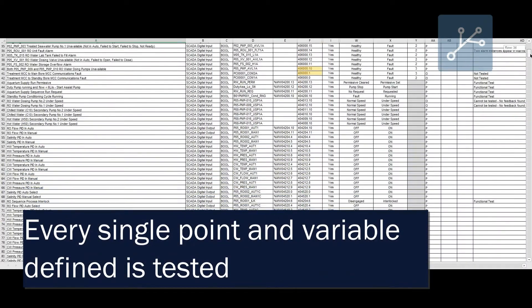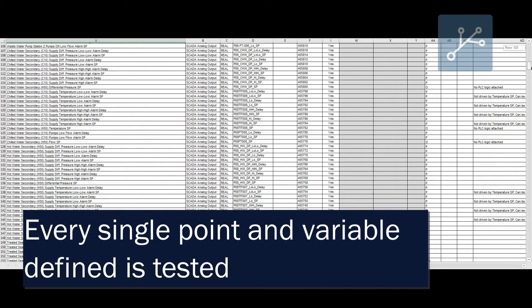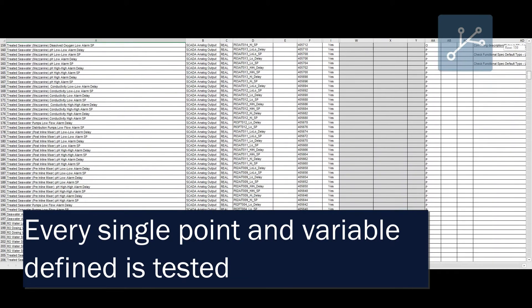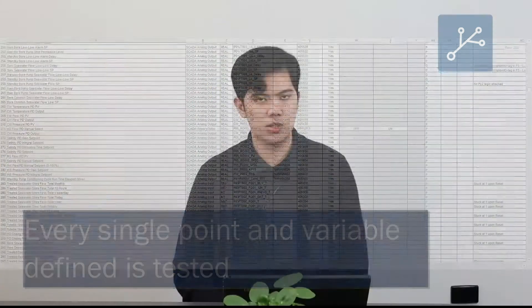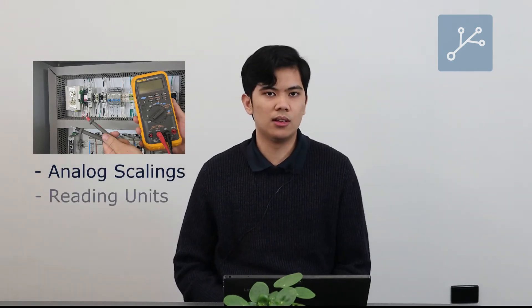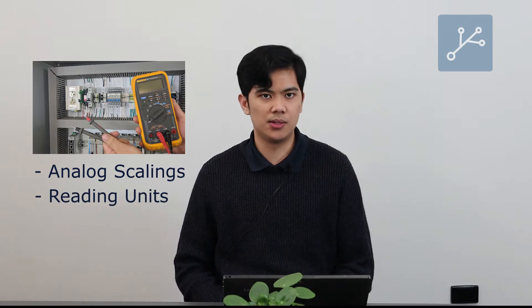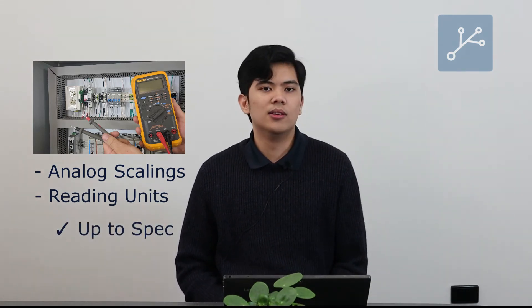We're really testing to see if we're getting the right values from the PLC and getting them correctly reflected into the SCADA system — making sure everything is addressed correctly and accurately, and that the scaling and units of the values in the SCADA system are within the specifications the client provided at the beginning of the project.